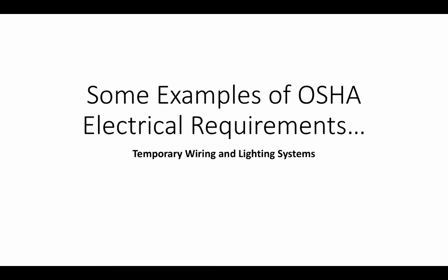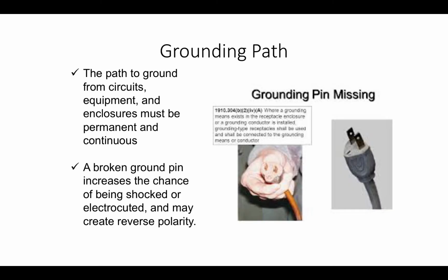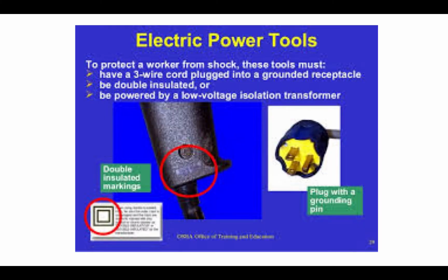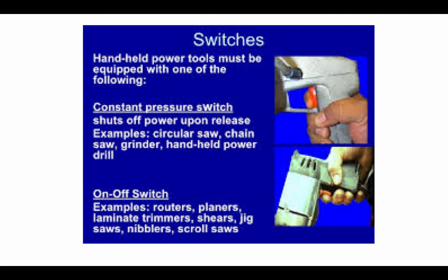Some examples of OSHA electrical requirements with regard to temporary wire and lighting systems. The path to ground from circuits, equipment, and enclosures must be permanent and continuous. A broken ground pin increases the chance of being shocked or electrocuted and may create reverse polarity because it can be put in upside down. You may not use any tool or any extension cord that has the ground pin broken or removed. To protect a worker from shock, these tools must have a 3-wire cord plugged into a grounded receptacle, be double insulated, or be powered by a low voltage isolation transformer. Okay, you need to be very, very careful on grounding pins.